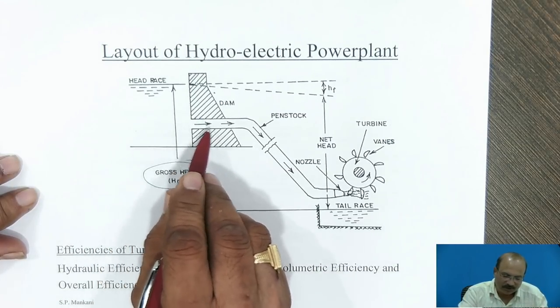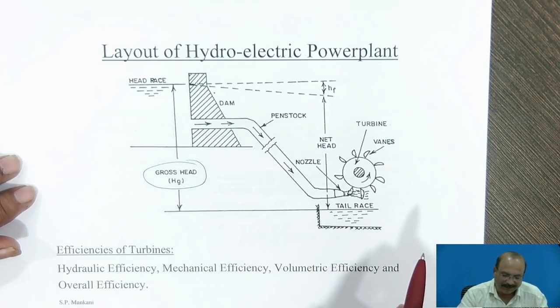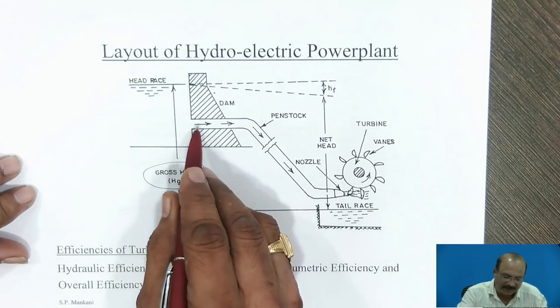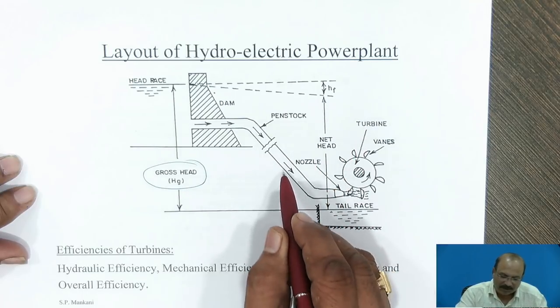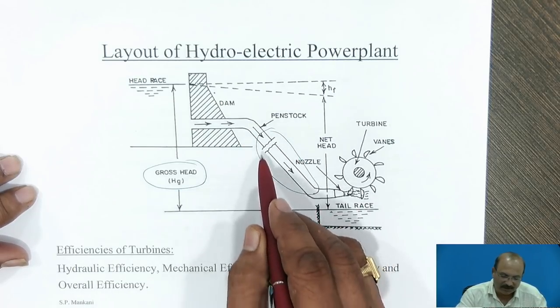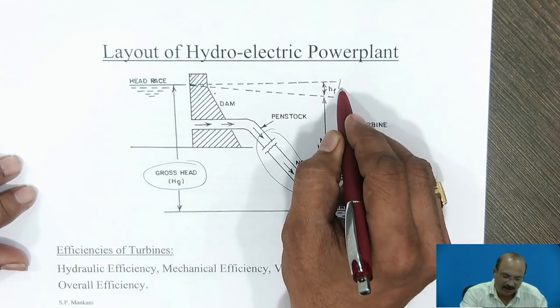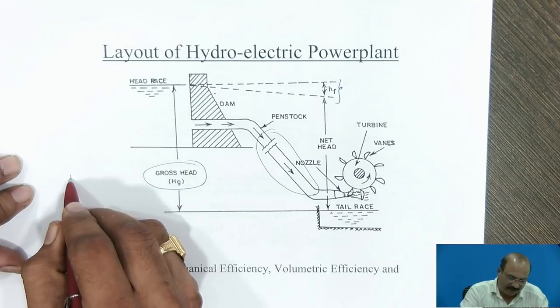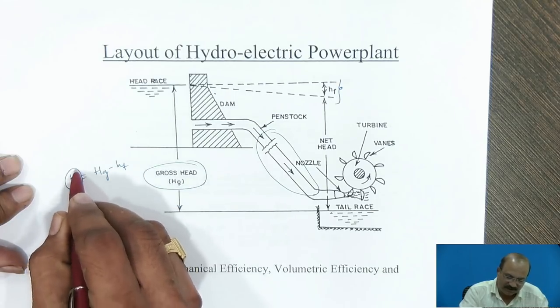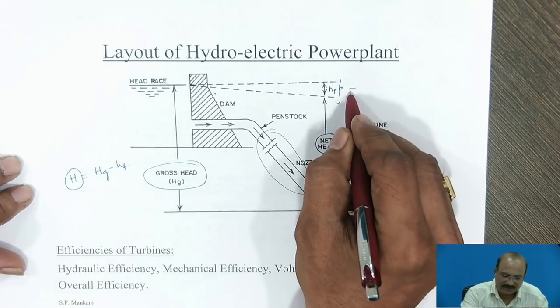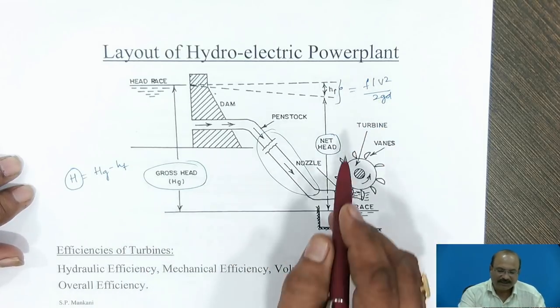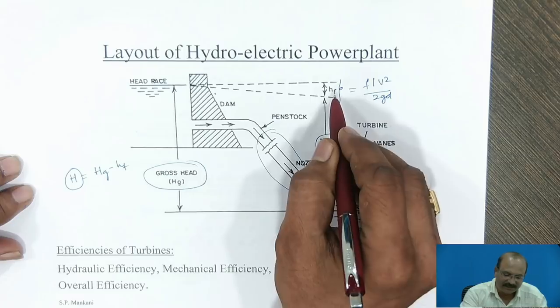The water flows through the penstock, which is made with metal as well as reinforcement. The water flowing through this pipe has frictional losses, and there will be additional losses acquired in the pipeline as well. Some of the losses are going to be neglected. The head loss due to friction is represented as HF. So, H equals HG (gross head) minus HF — this H is the net head. HF is given by FLV² upon 2GD.